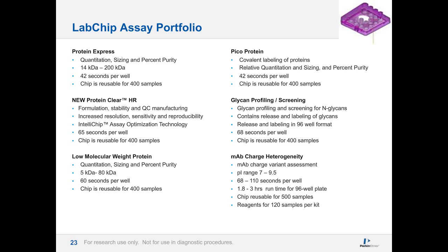Our new Protein Clear assay is the newest in our protein portfolio, really for formulation, stability, QC, and manufacturing needs. It has increased resolution via a longer separation channel, increased sensitivity, and better detection for low-level impurities, achieved by optimization of the on-board dye in the chip. We have better CVs around the lower impurity levels, and reproducibility and repeatability are achieved using the intelligent features Anubhav described. With the longer separation channel, it is 65 seconds per well — still very high throughput and especially faster than traditional CE-SDS methods.